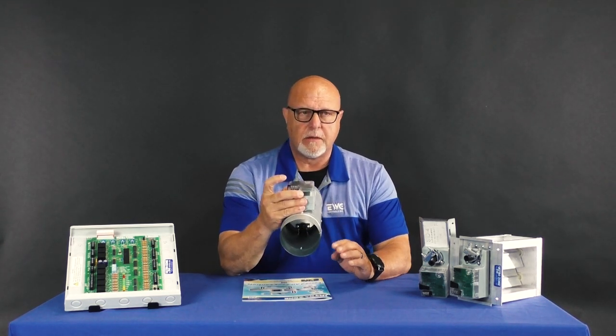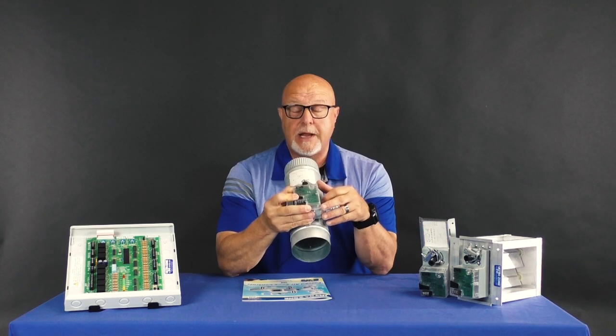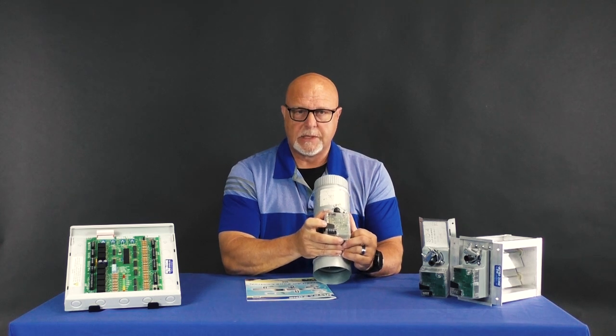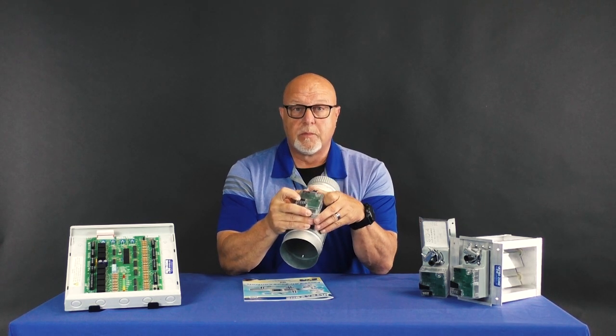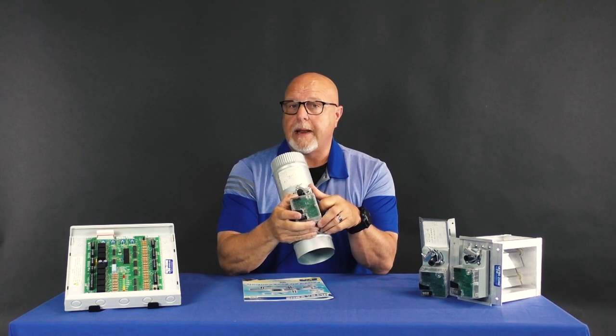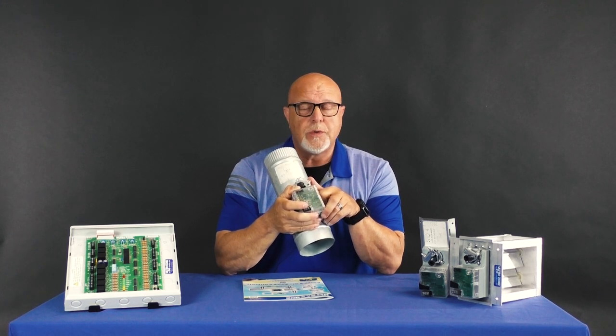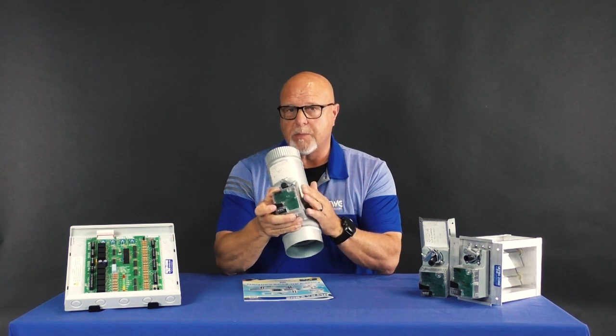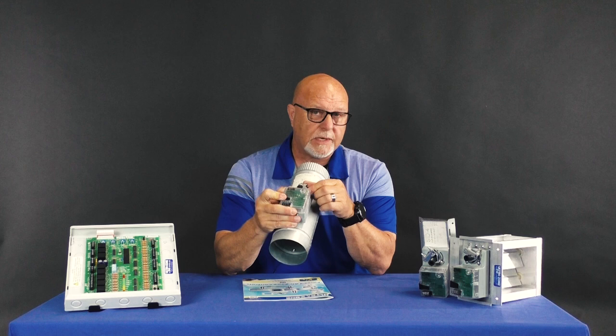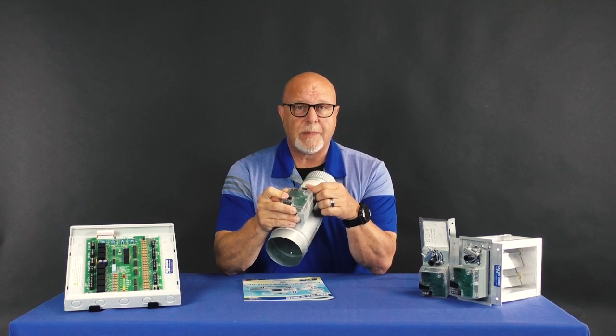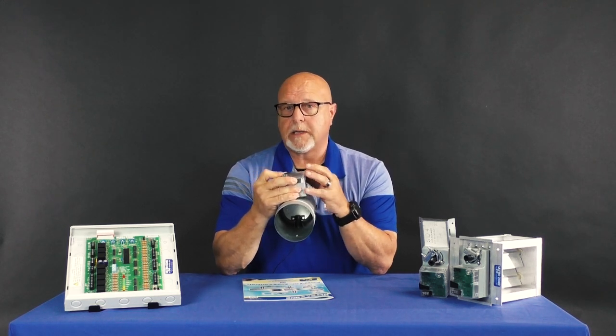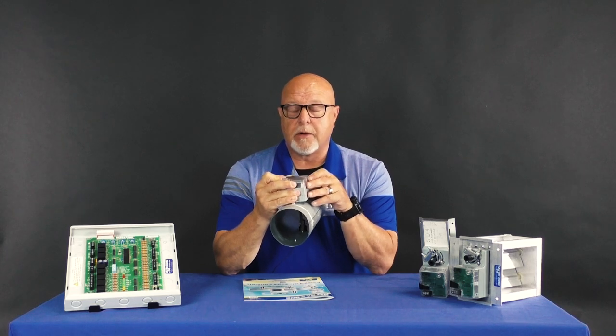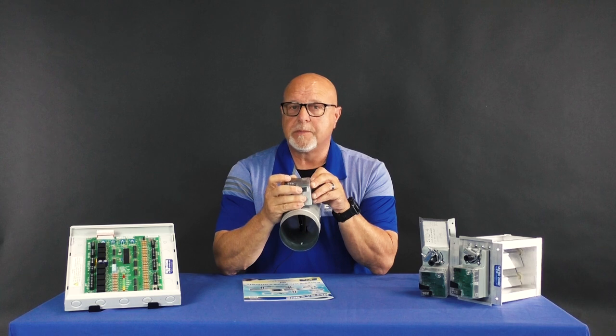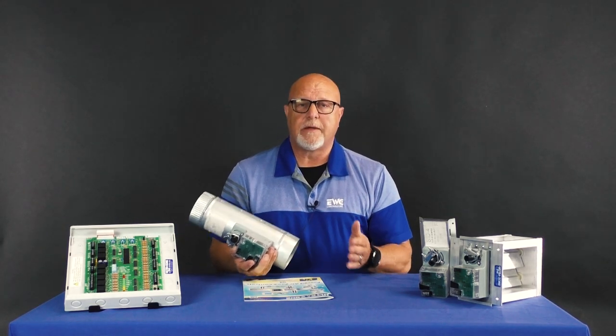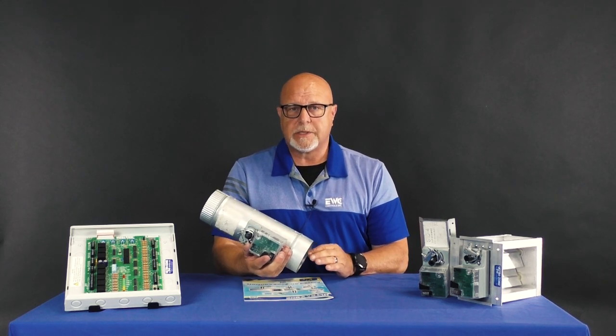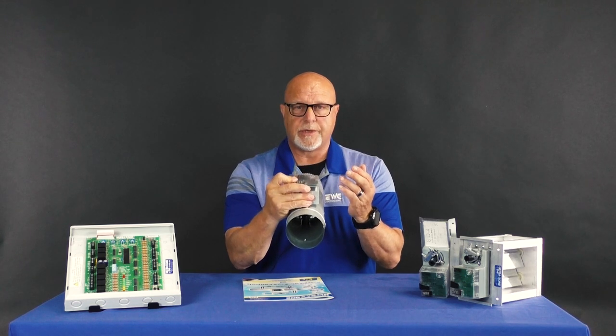If you notice that I was manipulating this damper with a manual gear button, a manual gear release. After this damper has been installed, you do have the ability to reposition the damper. As a contractor, knowing that our dampers rest in the open position, when you are checking out or commissioning the system to see if everything is working properly, you can force my damper, when no call for heat or cooling is there at the control board, to the closed position, and my damper will automatically rotate back open because it knows there's no power there or there's no call for heat or cooling. It will automatically rotate back to the open position, thereby allowing you to see if the damper is operating correctly, if it's jammed or it's hung up. All those situations can be quickly determined with just moving that damper to the closed position and watching it go back.